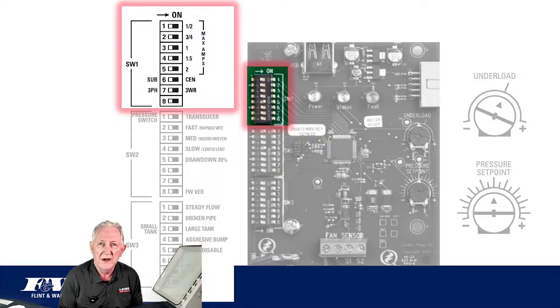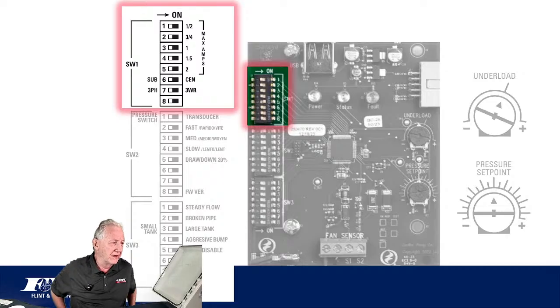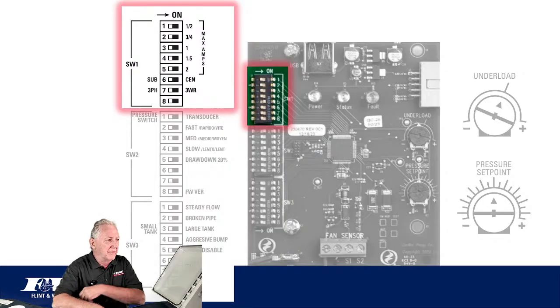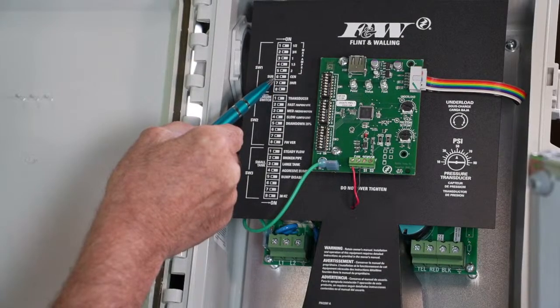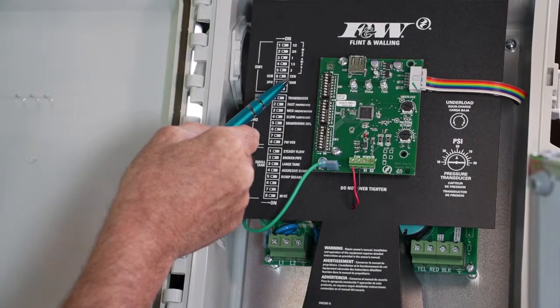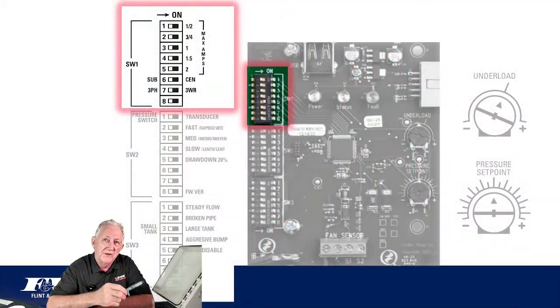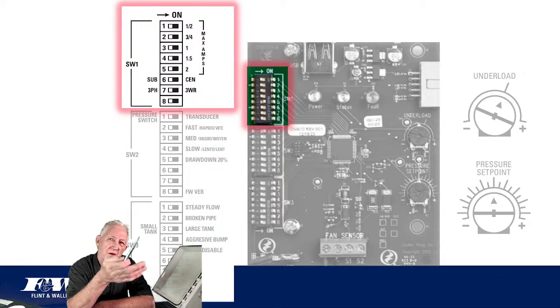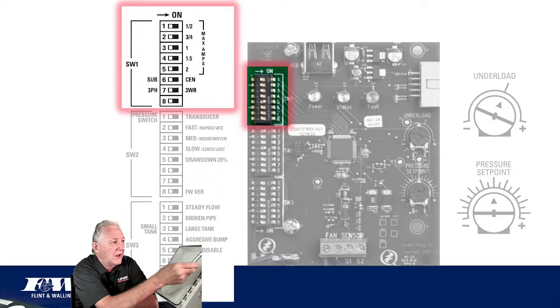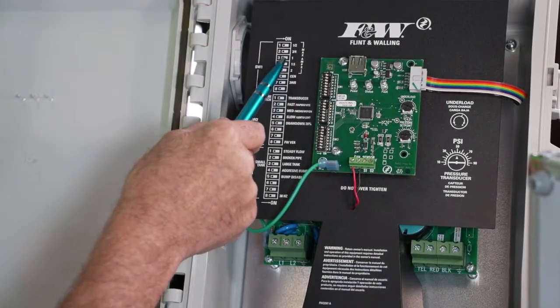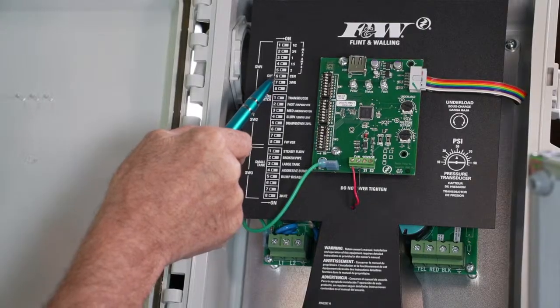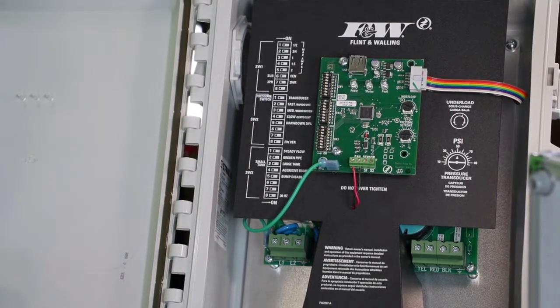So you can look at that SW1. All right, you've got your horsepower listed up there. That'll go from a half to a 2 horsepower on a 3-wire motor. Then just below that, those first 5 dip switches, position number 6 there. Position number 6 is going to indicate whether we're going to run a submersible pump or a centrifugal pump, all right? So let's just run on the premise that we're going to run a submersible pump motor with this. Let's just also run on the premise that we're going to select, I don't care, a horse and a half or 2. We're going to have to move one of these from the off position to the on position depending upon what horsepower we're going to pick, and we're going to leave position 6 right where it's at because it's going to indicate that it's a submersible pump that we'll be running.